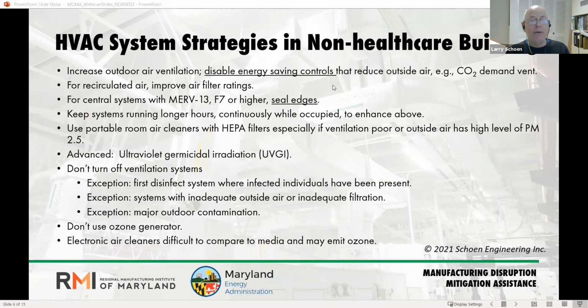Now, on those portable room air cleaners, as I said, even if you have a space that you can't ventilate with outdoor air, the use of portable room air cleaners with HEPA filters can reduce the particulate load. In a central air handler, we don't recommend a HEPA filter because they have high pressure drops. You can do almost 95% versus 99.7%. You can do almost the same job in a central air handler with a good MERV filter. But on these standalone filters, they're already rated with a fan that can push the air through a HEPA filter. So that's why I have the HEPA listed here. And they can do a good job.